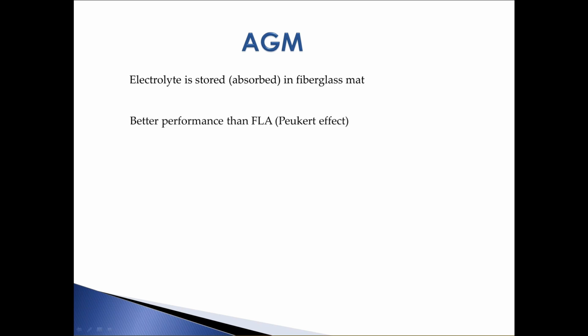The performance is better than the flooded lead acid or the gel cell if you take into account the Peukert effect, so you get more usable energy at high discharge rates. They're maintenance free just like the gel cell unless they are abused and you cause them to outgas. They have the longest life of any of the lead acid batteries, about 1750 cycles on a good one, but they do cost more money.